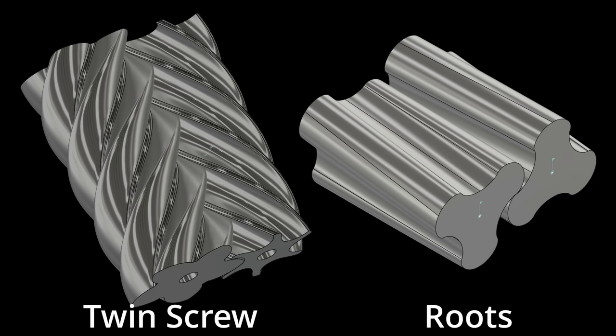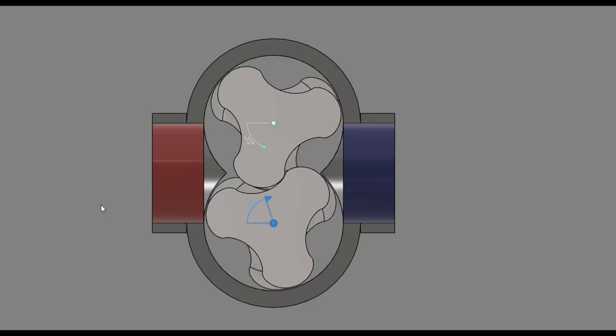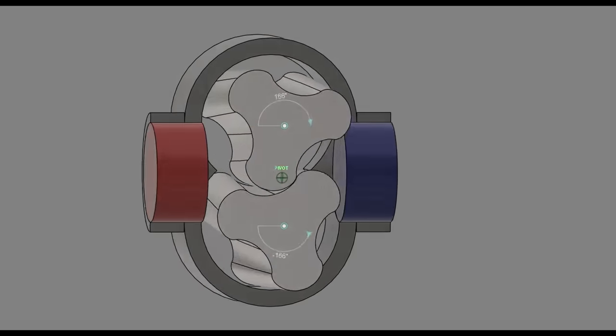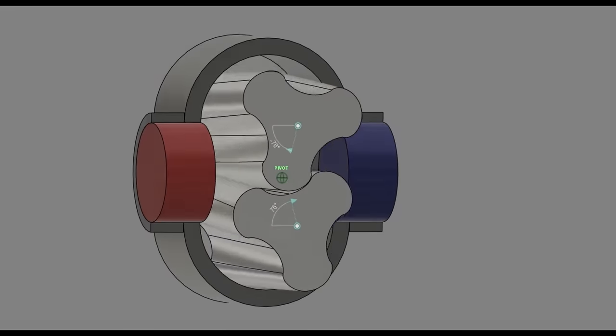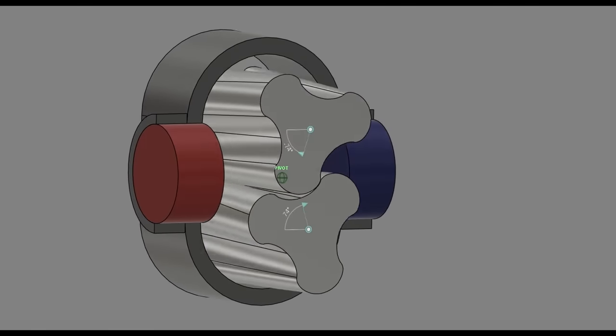Previously, a lot of people were confused about the differences between a twin screw compressor like this and a Roots style compressor. In a Roots style compressor, air enters perpendicular to the rotors, usually right in the middle of the rotors, and the inlet and exhaust ports are directly across from each other.